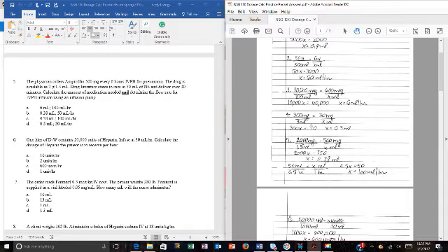So we know that we're going to give this 50 milliliters over 30 minutes, okay? So the 50 milliliter bag we're giving over 30 minutes, and I need to know how to program the pump. So the pump is set up to program how many milliliters per hour. So that's simply what I'm figuring now. If 50 milliliters go in a half an hour, how much is going to go in an hour? So that's 100 milliliters per hour.